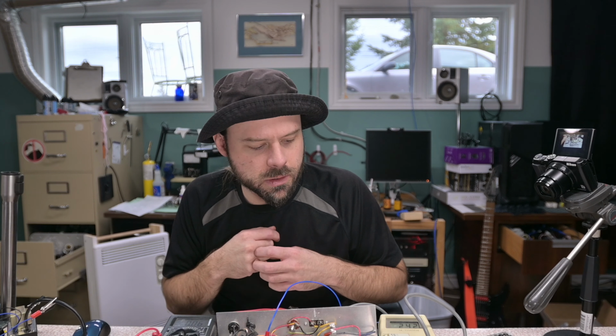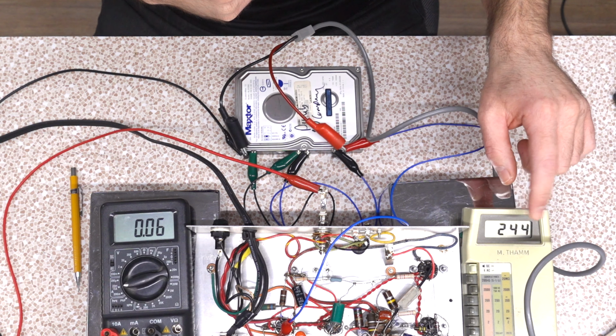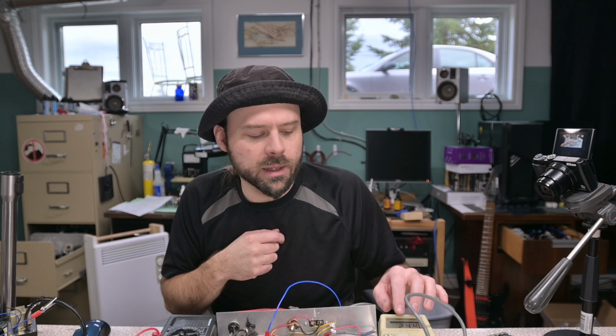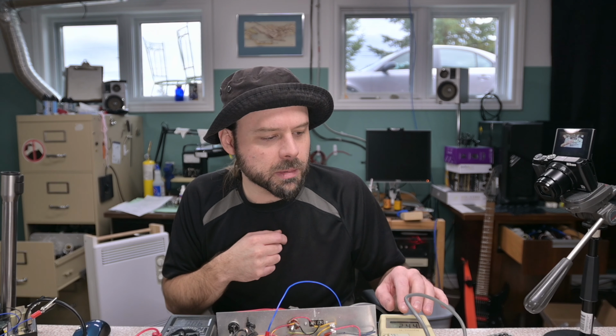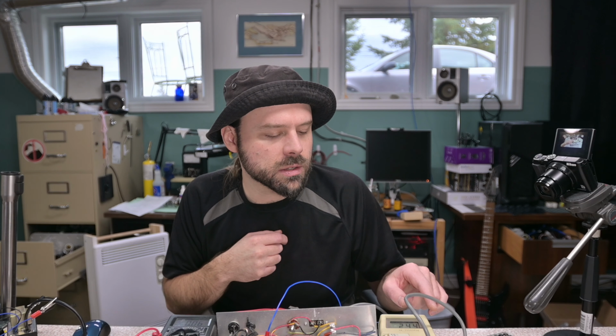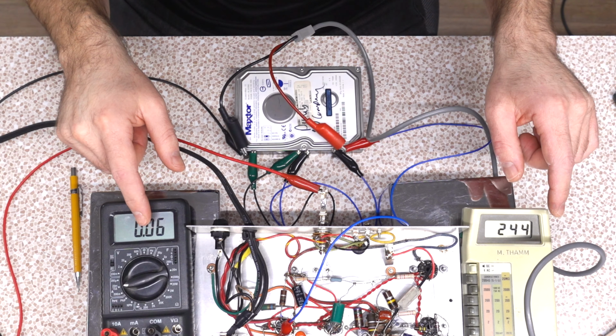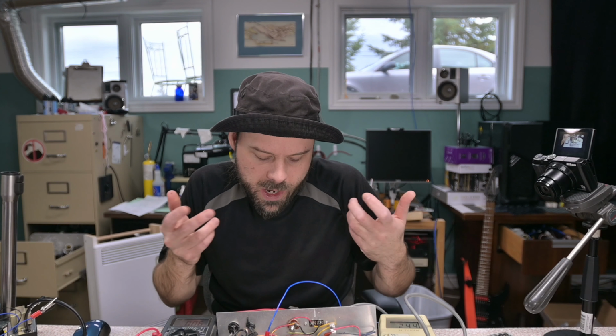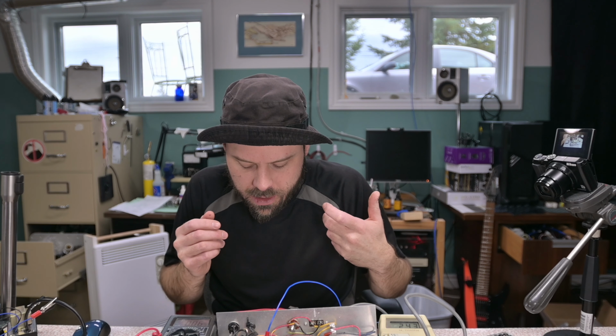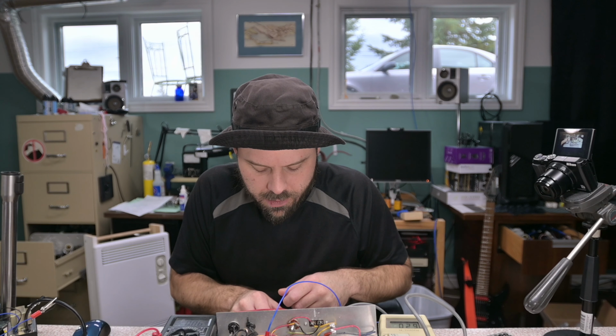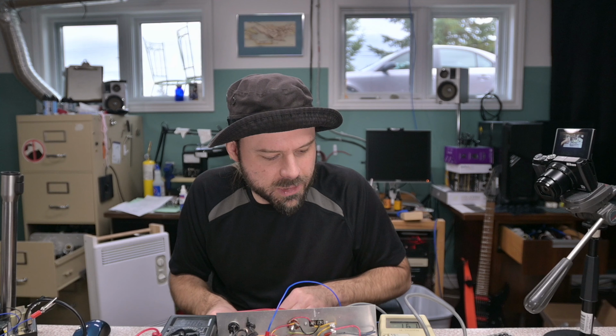Now 243 volts, that's more in line with a proper voltage drop coming down from half of 332. Still says it's putting a fair load on there, and we're only pulling from one side of the secondary, so we're not necessarily getting the accurate representation. We're just basically getting ourselves in the neighborhood.